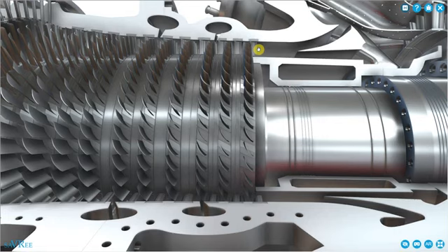With aeroderivative engines, it's actually higher. It might be 30 to 1. Those types of gas turbine are more focused on generating thrust compared to the heavy frame design where we're focused on generating electrical power, or at least that is our end goal. Aircraft require thrust in order to stay up in the air. Power plants require as much power as possible in order to be profitable.